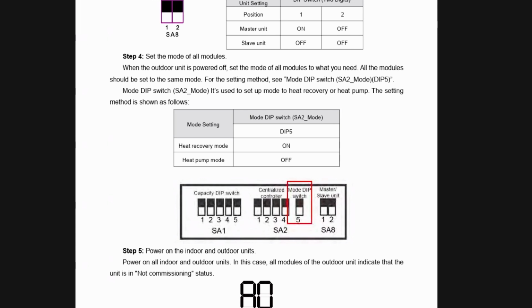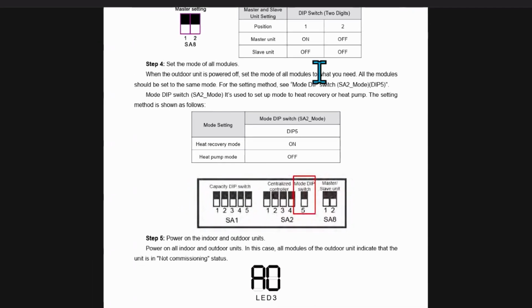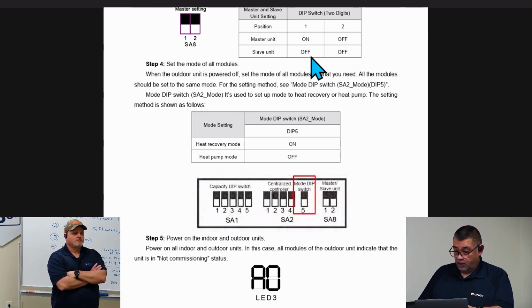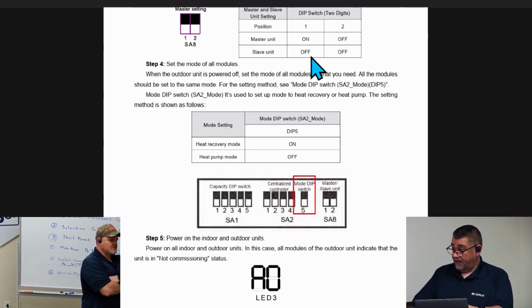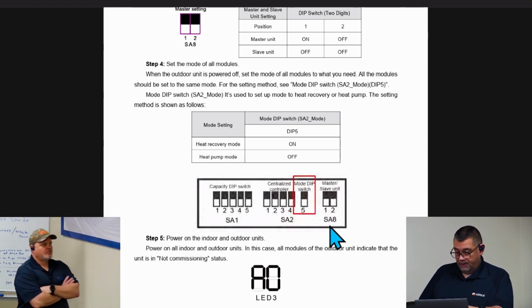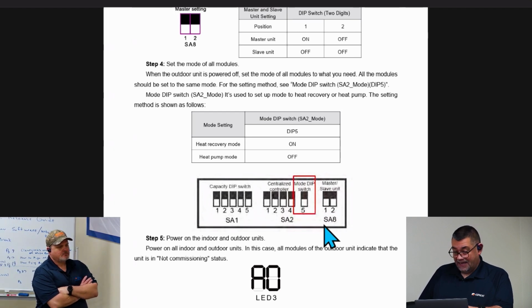Yep. So make sure you cover master slave. When you are dealing with twinned units, when you have two outdoor units and you're piping them together, you need to determine what is the master and what is the slave unit. As an example, a combination of a 14-ton where you're using a 6 and an 8, you pipe them together, go into the unit and change the second unit to a slave. Correct. The first one is automatically set from the factory as the master, and what we're talking about here is dip switch setting SA8. If you notice here at the bottom, that's where the configuration needs to be changed.